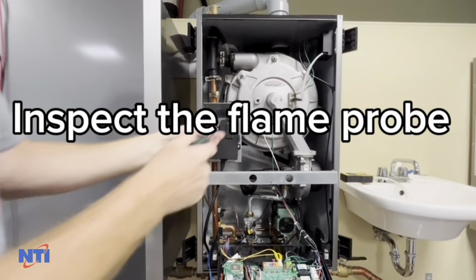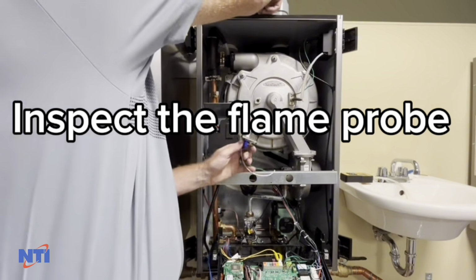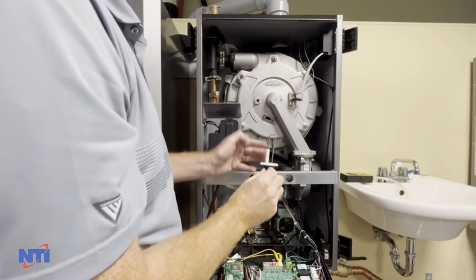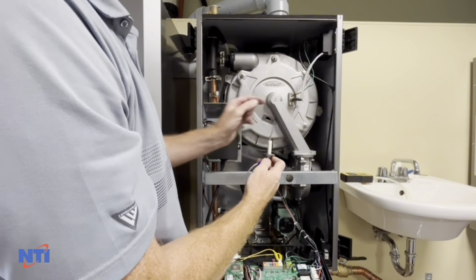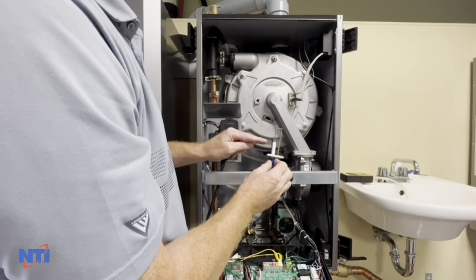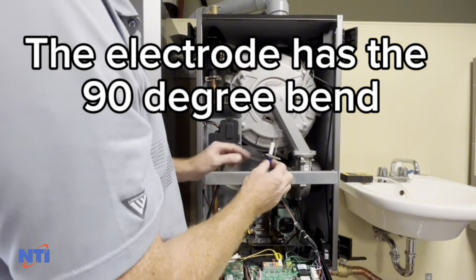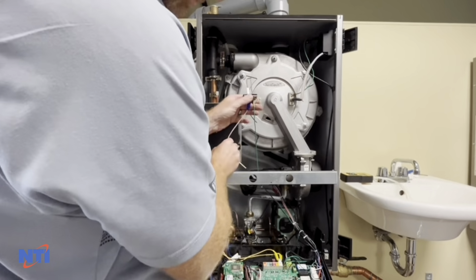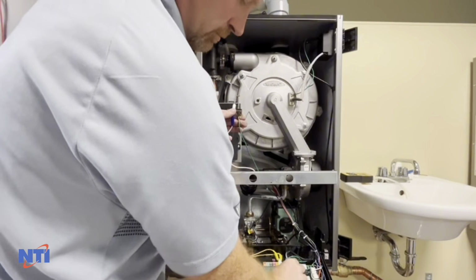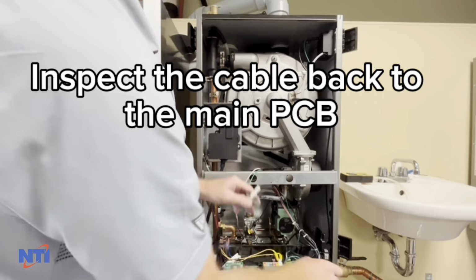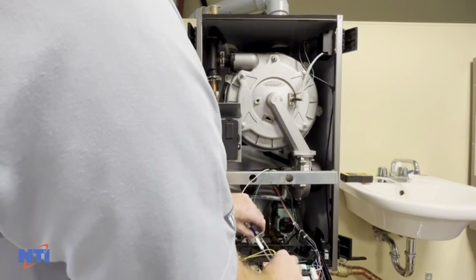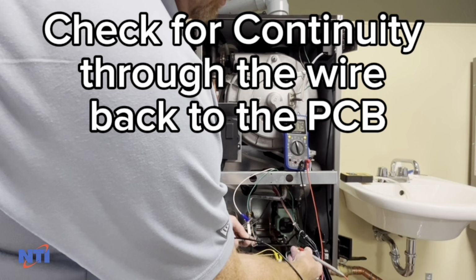Next, inspect the flame probe. Remove the flame probe. The wire is part of the assembly. The portion with the 90-degree bend is the electrode and is what detects the flame. Look for severe warps or cracking of the insulator. Trace the wire back to the main PCB. Check for continuity. The resistance should be very low.